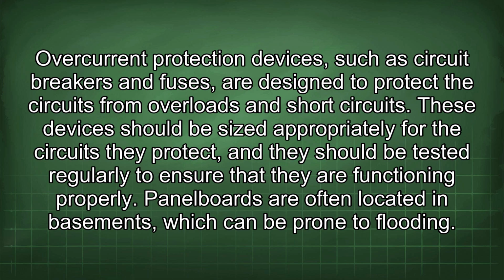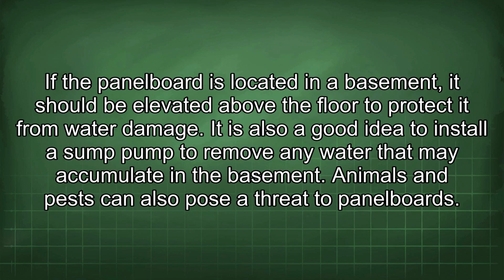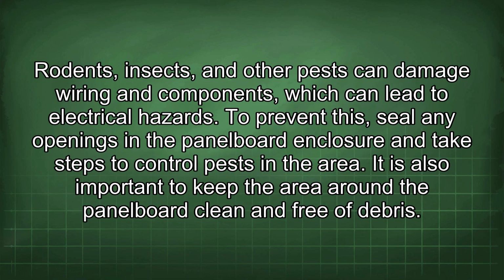Panel boards are often located in basements, which can be prone to flooding. If the panel board is located in a basement, it should be elevated above the floor to protect it from water damage. It is also a good idea to install a sump pump to remove any water that may accumulate in the basement. Animals and pests can also pose a threat to panel boards. Rodents, insects, and other pests can damage wiring and components, which can lead to electrical hazards. To prevent this, seal any openings in the panel board enclosure and take steps to control pests in the area.